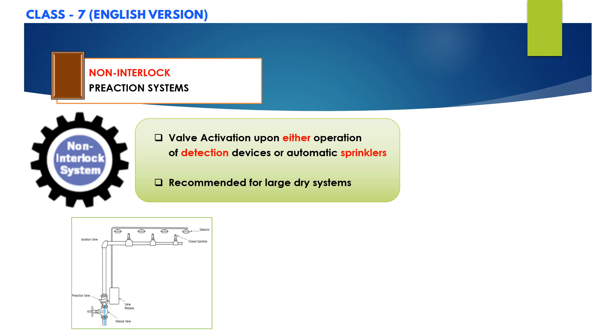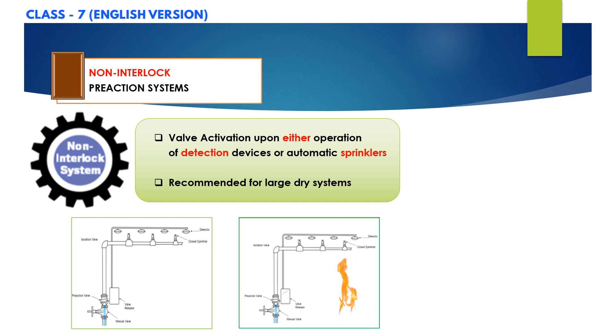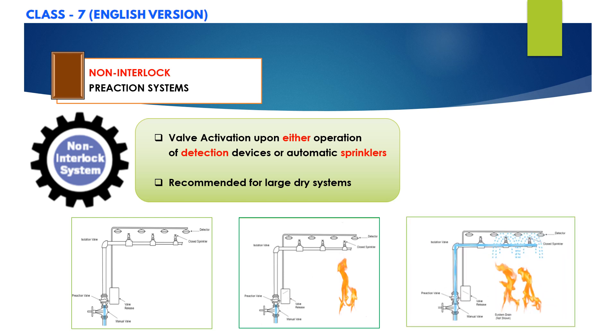In these systems, the deluge valve will open when either the detection system operates or a loss of pneumatic pressure in the sprinkler system occurs. When the deluge valve opens, water will flow into the sprinkler piping and any other opening on the system. An advantage of this kind of system is that if the detection system fails to operate or malfunctions, the system can operate as a dry system.